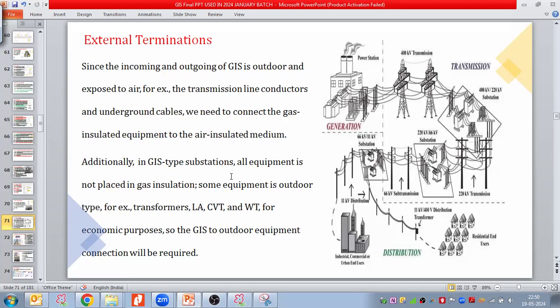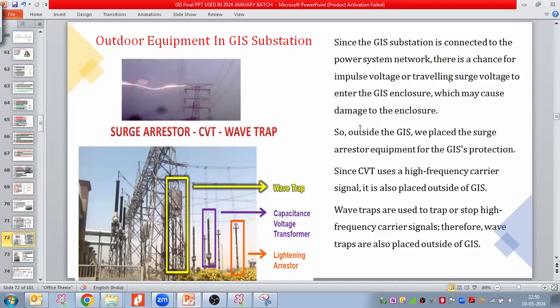Additionally, in GIS type substations, not all equipment is placed in gas insulation. Some equipment is outdoor, for example the transformer, surge arrestor, CVT and wave trap, for economic purposes. So GIS to outdoor equipment connections will be required. How do we do these terminations? Since the GIS substation is connected to the power system network, there is a chance for impulse voltage or traveling surge voltage to enter the GIS enclosure, which may cause damage to the enclosure.